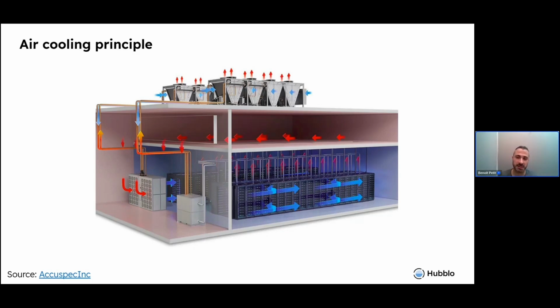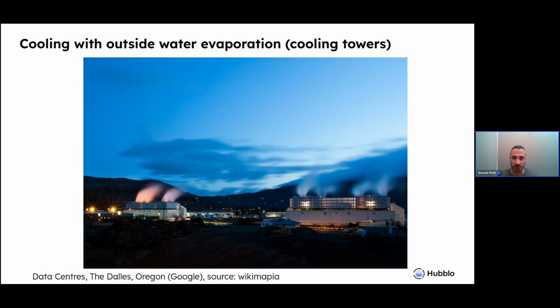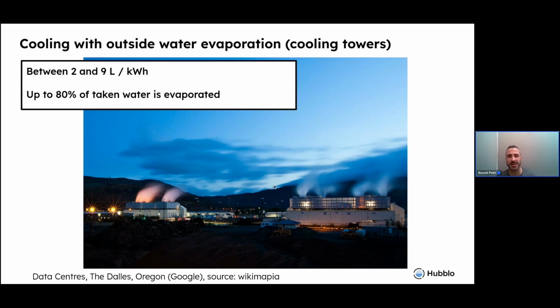But the problem regarding air cooling is that it can't keep up with more energy intensive use cases. So because of that, what you might see in hyperscaler data centers, the bigger data centers, is cooling with the help of outside water evaporation through cooling towers. So this type of cooling system exists a lot in the US, not necessarily in France, because in France there are various regulations that prevent the use of cooling towers. And this is a solution that can be more energy efficient than a full air cooling solution, but this consumes a lot of water. So it's between 2 and 9 liters of water consumed for each kilowatt hour of energy.